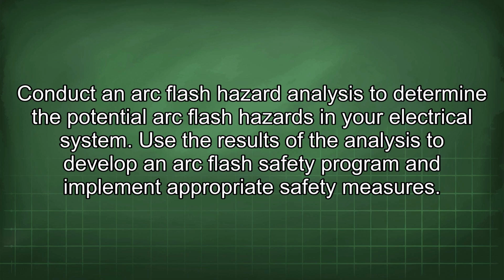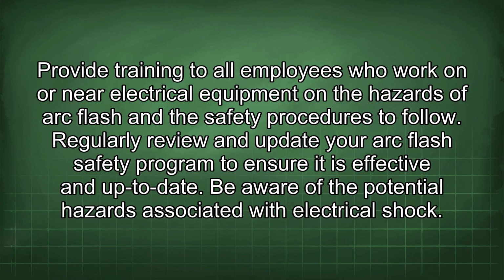Conduct an arc flash hazard analysis to determine the potential arc flash hazards in your electrical system. Use the results of the analysis to develop an arc flash safety program and implement appropriate safety measures. Provide training to all employees who work on or near electrical equipment on the hazards of arc flash and the safety procedures to follow. Regularly review and update your arc flash safety program to ensure it is effective and up to date. Be aware of the potential hazards associated with electrical shock.